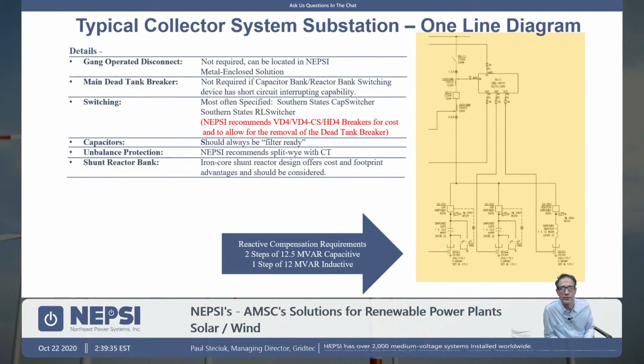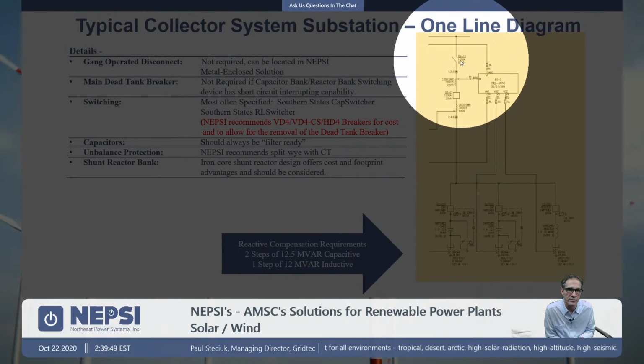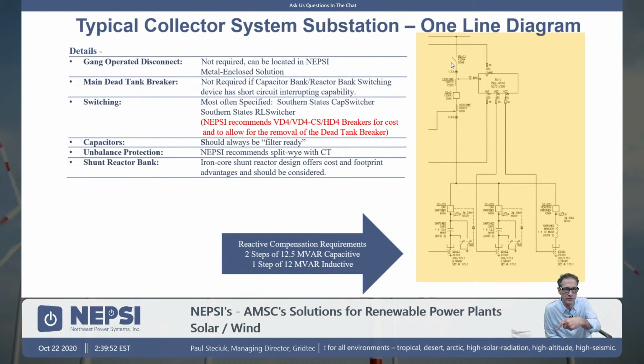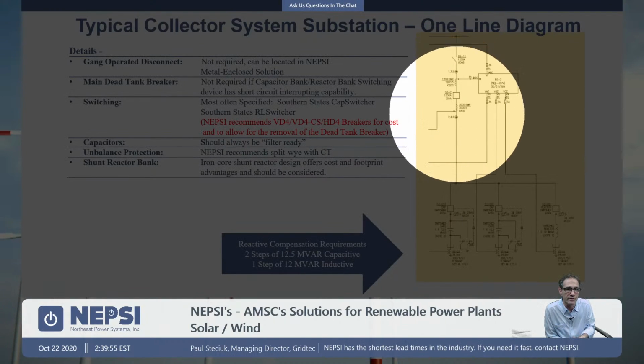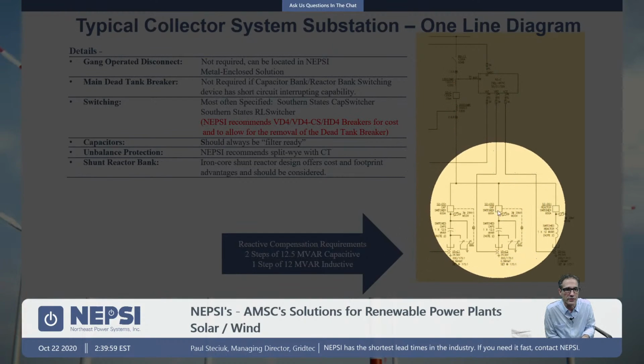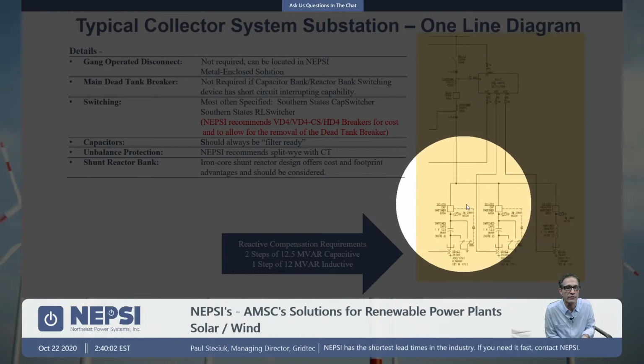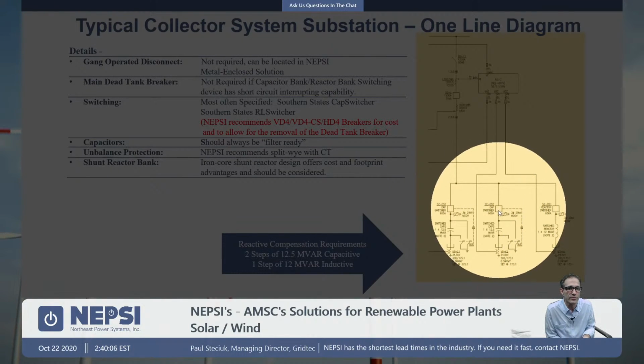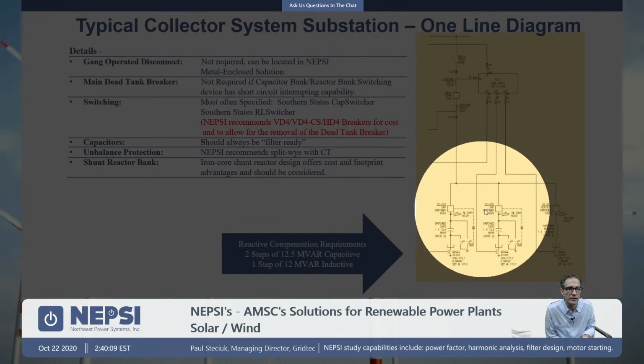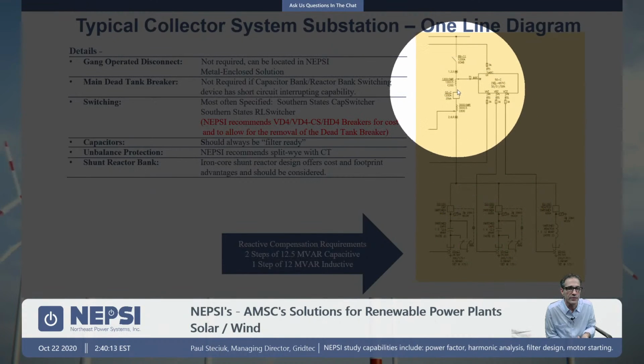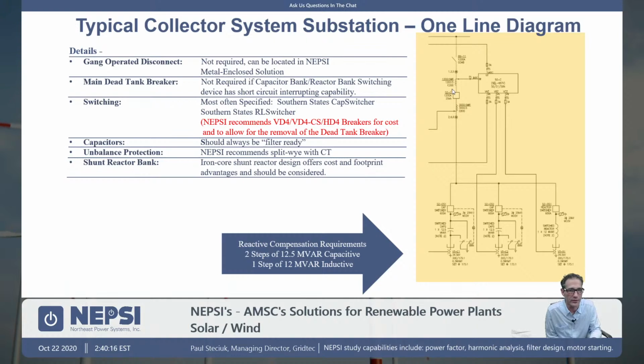And there are some cost-saving opportunities here. This is an open-air design. This was a project that we were asked to bid as an alternate to an open-air design. The first thing I'd like to note is we could eliminate this disconnect up here and put that disconnect into our enclosure. We could also eliminate this breaker if we were to eliminate the cap switchers here and install VD4 CSs or VD4 breakers instead. If we put the short circuit protection down here inside these as breakers, we can eliminate this breaker up here. That could be anywhere between, say, I don't know, $30,000 or $50,000 in installed costs in the project. Plus you've got your actual gang operated switch there.